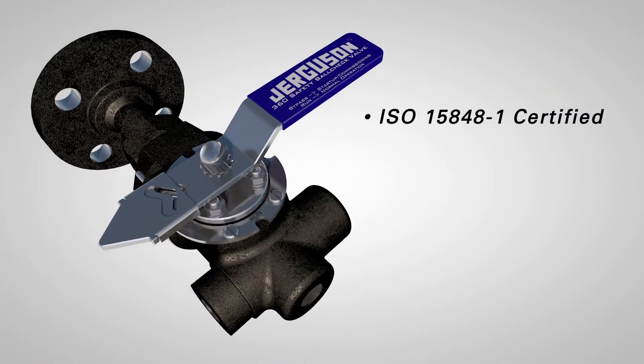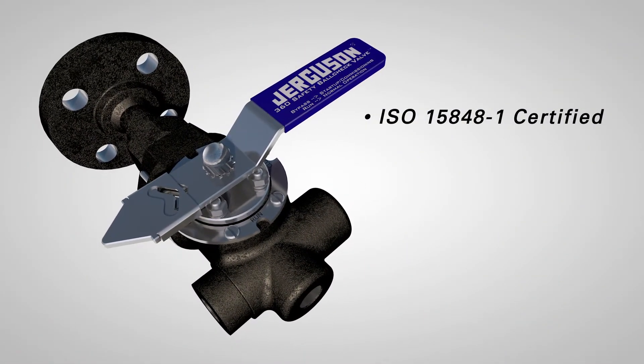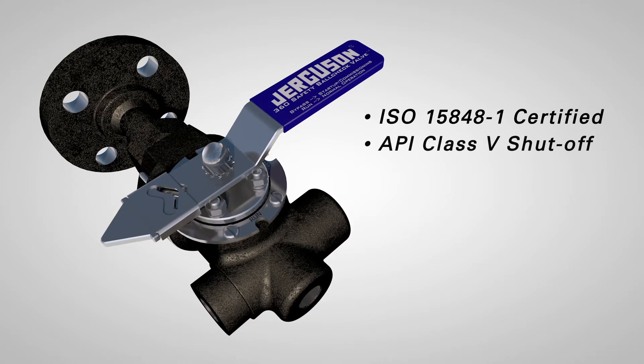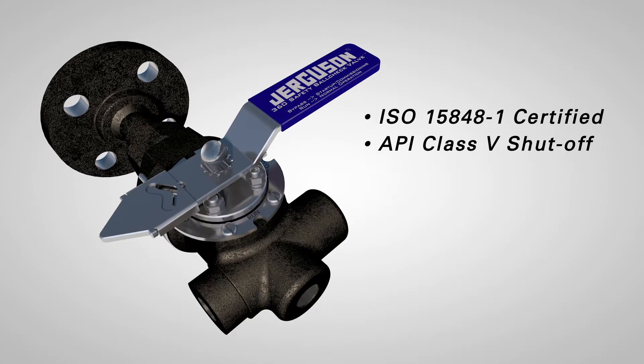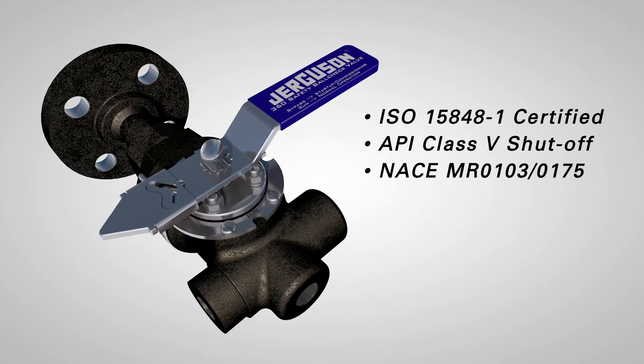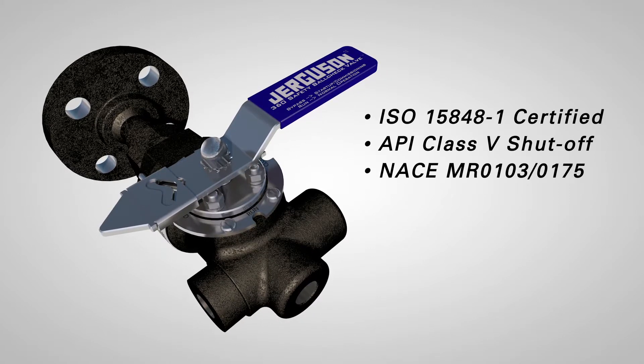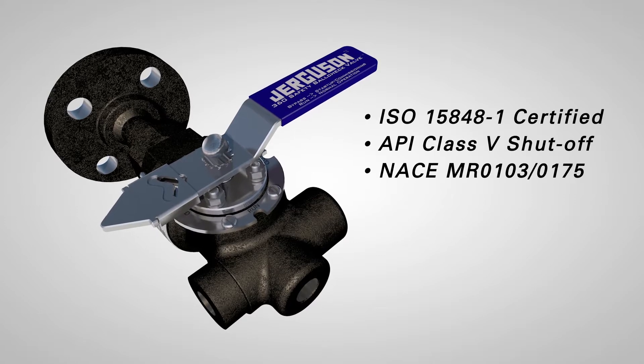All valves are certified to ISO 15848-1 for low emissions, meet API class 5 shutoff requirements, and all wetted components comply with NACE MR0103 and MR0175 as standard.